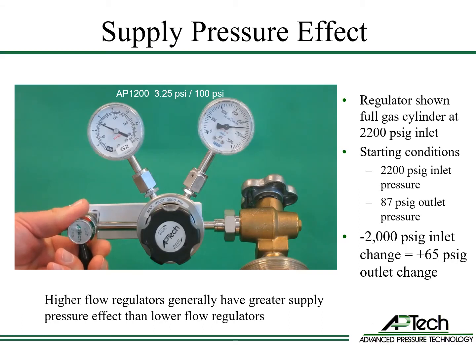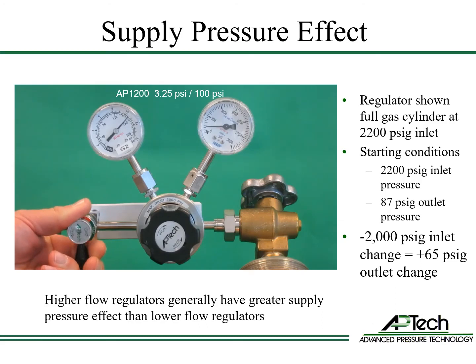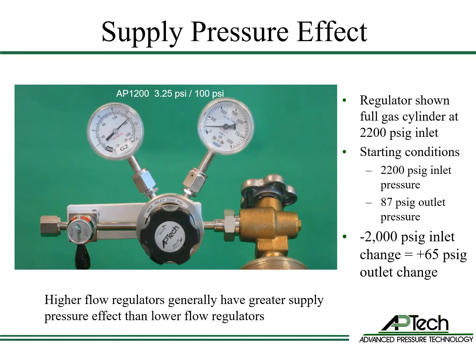Now let's look at supply pressure effect in an AP1200 regulator. In this example, the inlet pressure is 2200 psi and the outlet pressure is 87 psi. As the inlet pressure drops to 200 psi — the pressure when cylinders are often changed — the outlet pressure continues to rise. The 2000 psi drop in inlet pressure causes a 65 psi increase in outlet pressure. The AP1200 supply pressure effect is 3.25 psi per 100 psi. Higher flow regulators generally have greater supply pressure effect than lower flow regulators.